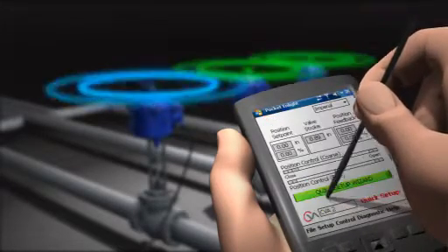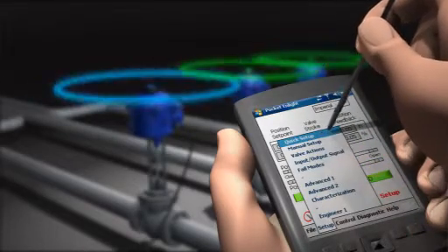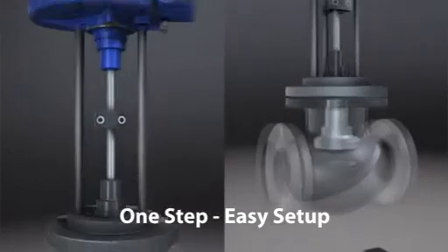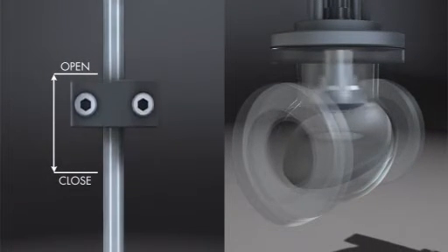The green indicator light on the addressed actuator turns to blue when Bluetooth communication is activated. The Quick Setup Wizard on the Bluetooth device enables the actuator to be rapidly calibrated for both closed and open positions.